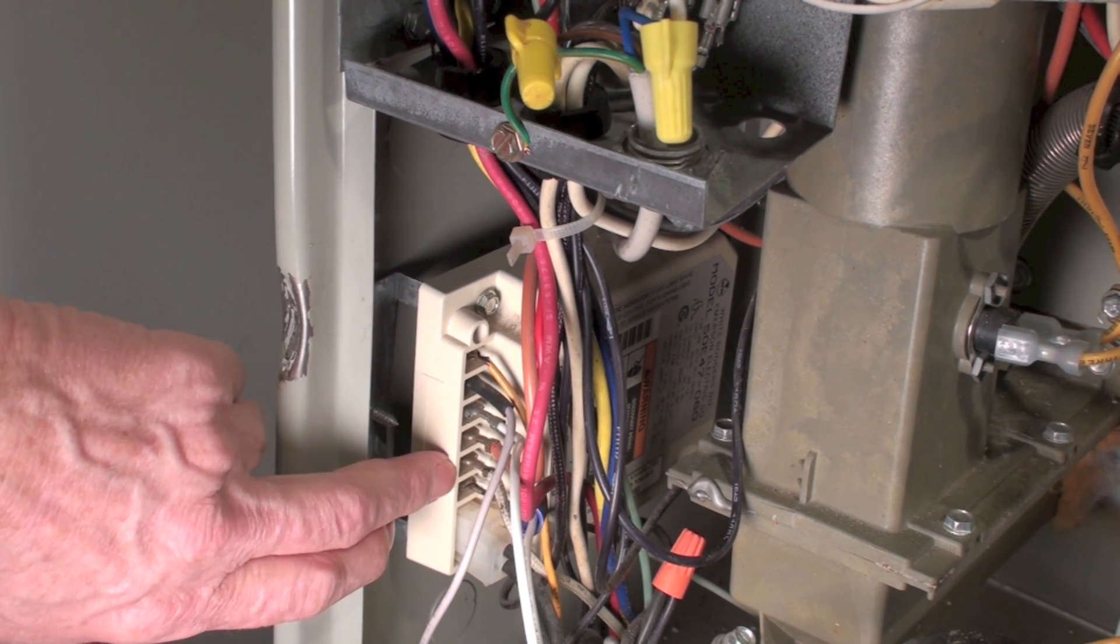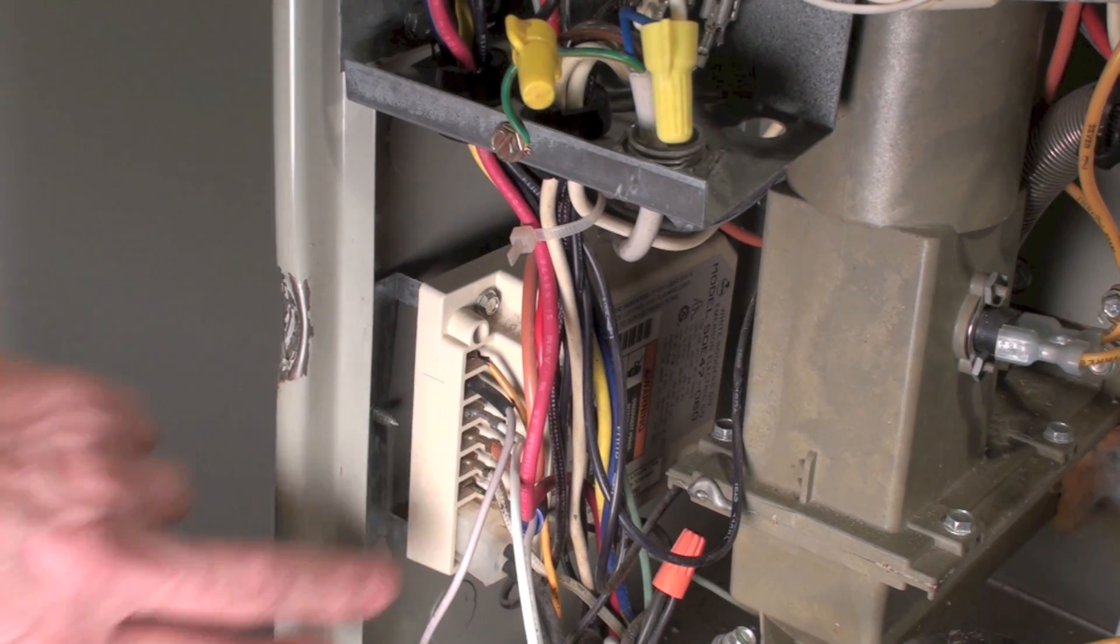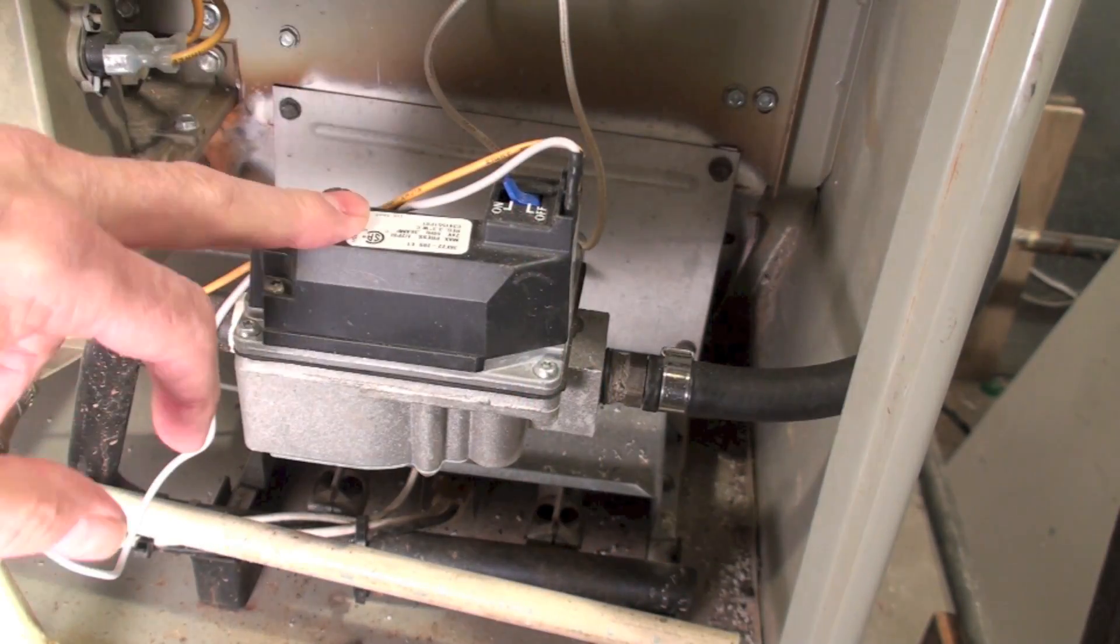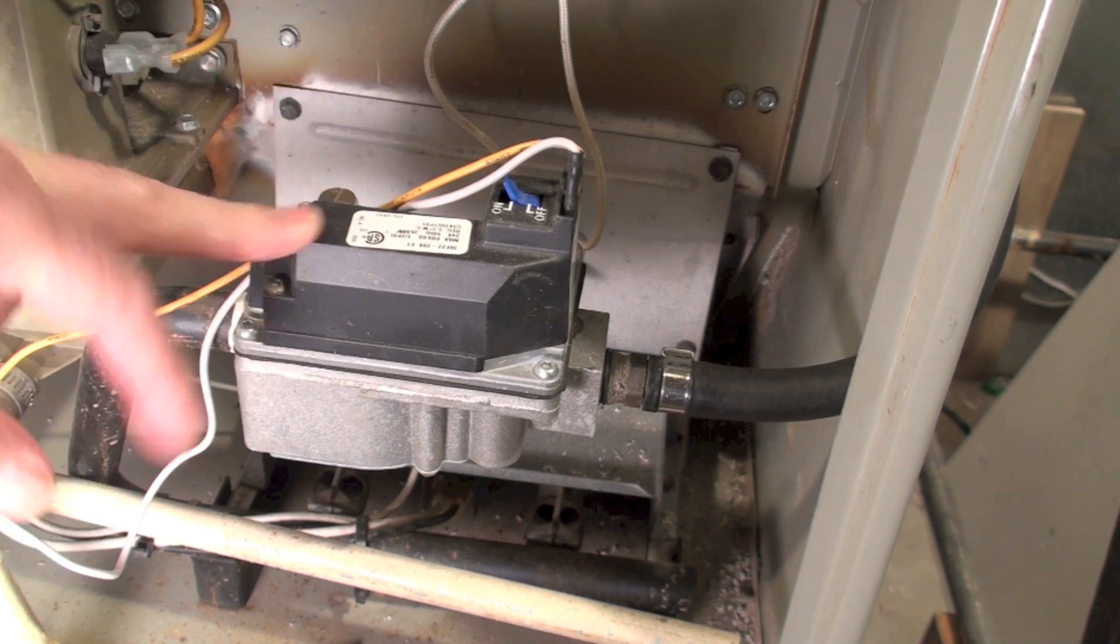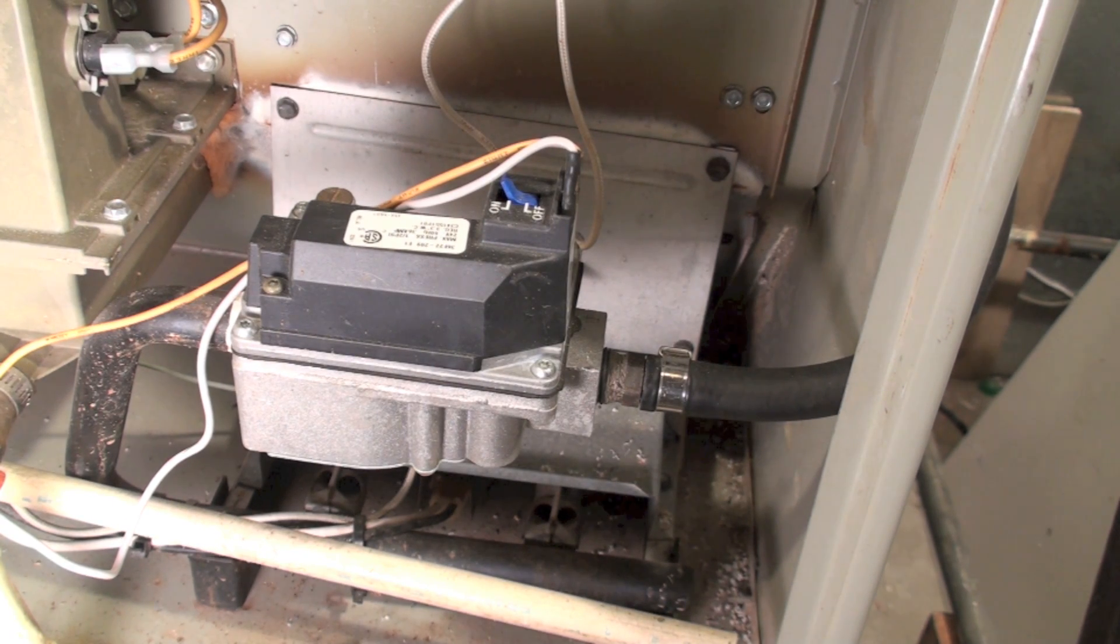That means the gas valve opens. It opens for, I think, about six seconds. Then the flame rod has to sense flame in that time, and if it does sense flame, it continues to operate.